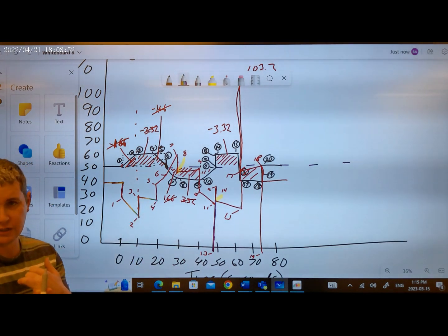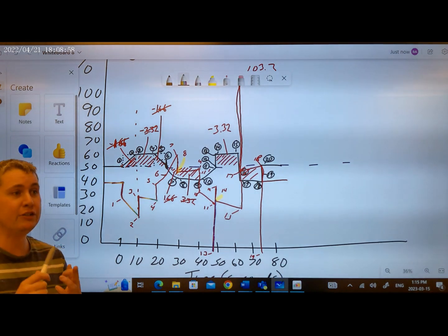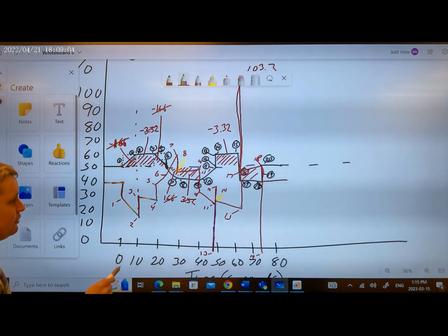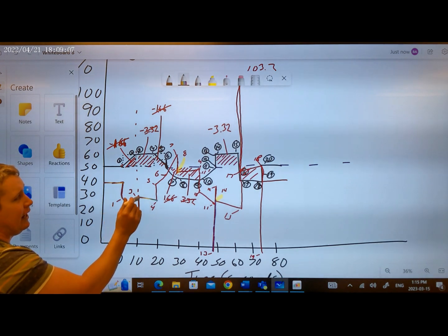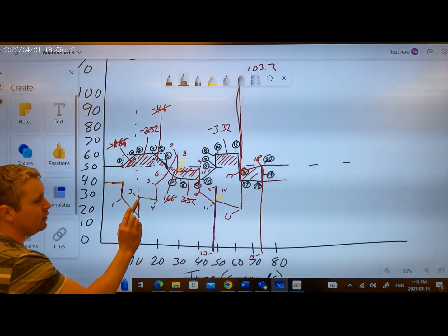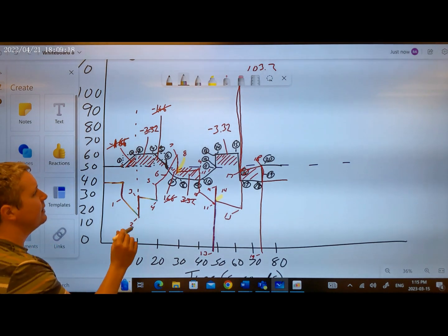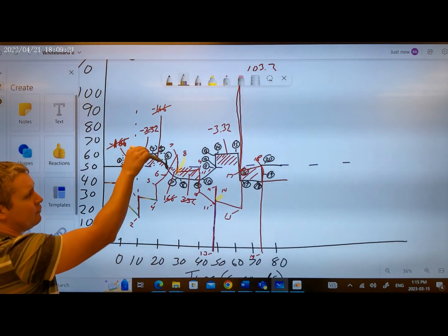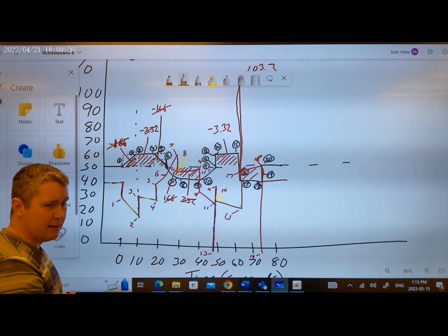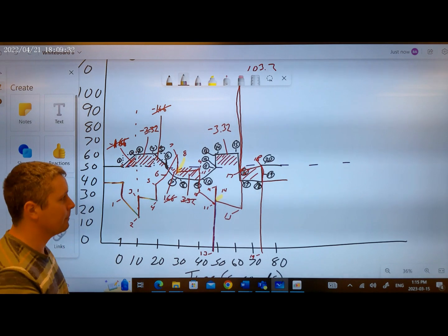Now, over the course of the next 10 seconds, you see our output trend down. There is no derivative because there's no ramp rate. There's no extra proportional, but we do have an accumulating integral, which we have to then account for. So that is why our output is saying, you still have positive error, you keep accumulating positive error, I'm going to keep giving you a little bit more negative of an output. Right? That makes sense. But now it starts to have a negative ramp rate. Our derivative instantaneously says, whoa, I don't like ramp rates. So we have derivative instantaneously.